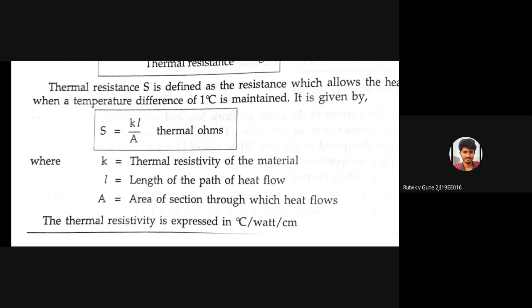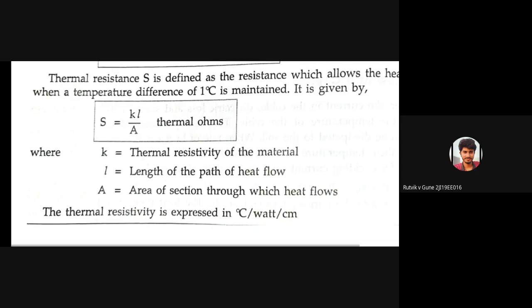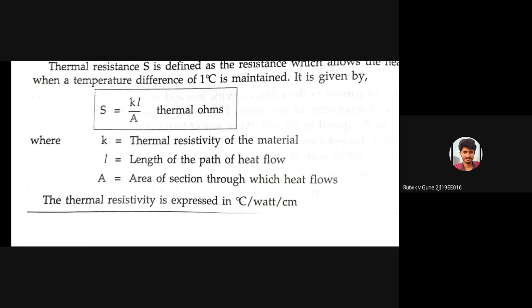Thermal resistance must be evaluated for underground cables and it differs for different cable types — it is different for a single core cable and different for a three core cable. Thermal resistivity is represented by small k, expressed in degrees Celsius per watt per centimeter.